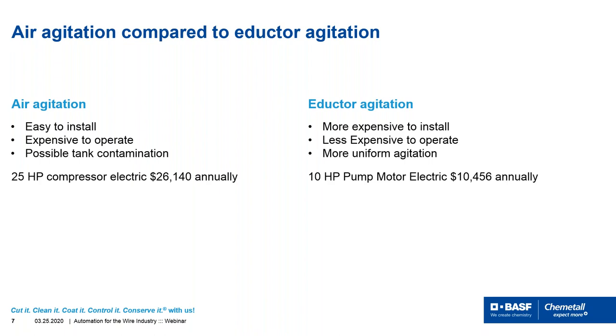One of the other problems associated with air agitation that I didn't touch on, besides being expensive, is that air sometimes has oil inside of it, has moisture inside of it, and the piping bringing the air in many older plants is usually black iron or carbon steel. Because of that, you have a lot of rust internal to that piping, and now we're bringing those contaminants into the tank we're agitating with our air. So you want to be cautious of that. You may want to filter the air before it goes into the tank to get those contaminants out, because it could present a problem for you later on.